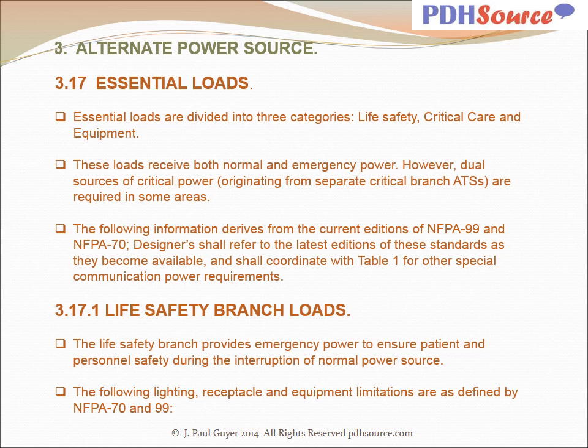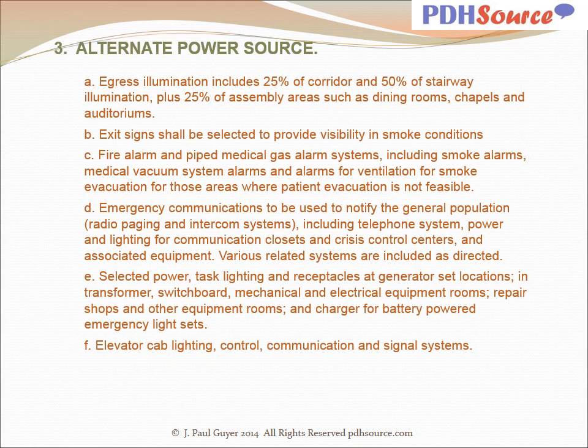The following lighting, receptacle, and equipment limitations are as defined in NFPA 70 and 99. Egress illumination includes 25% of corridor and 50% of stairway illumination, plus 25% of assembly areas such as dining rooms, chapels, and auditoriums. Exit signs shall be selected to provide visibility in smoke conditions. Fire alarm and piped medical gas alarm systems, including smoke alarms, medical vacuum system alarms, and alarms for ventilation for smoke evacuation for those areas where patient evacuation is not feasible. Emergency communications to be used to notify the general population, radio paging, and intercom systems, including telephone system, power and lighting for communication closets, and crisis control centers and associated equipment. Various related systems are included as may be directed by the owner.